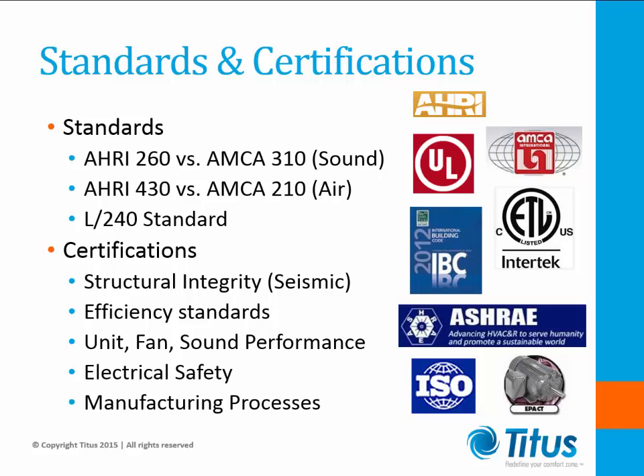Initial points of interest within the AHU is how reliable are the performances. Many of the air handling units that are found in the industry are measured in two different methods, AHRI or possibly AMCA. The AHRI standard is for the entire unit itself, whereas AMCA standards apply only to the fan. It is our goal to look at the AHRI ratings for the entire air handling unit on a whole. The more familiar ones would be the AHRI 260, 410, and 430 standards.